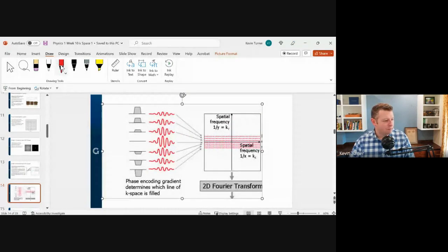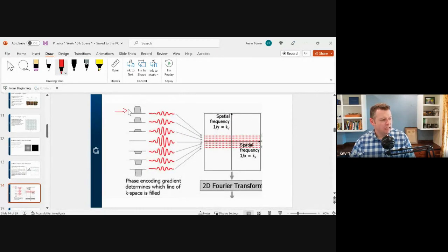So if we look at our different applications of the phase encoding gradient here, as the phase encoding gradient becomes more steep, we can see these echoes have lower peaks, which means they have less SNR. When we get down here where we don't have the gradient turned on at all, we have very strong peaks. So those echoes we want to put towards the center of K-space, where the echoes out here that are very weak, we are going to put towards the outside of K-space. Right? So as we run our pulse sequence, we are changing the steepness of the phase encoding gradient with every echo. Every echo looks unique. Every echo goes a different place in K-space. Strong echoes towards the center, weaker echoes towards the outside.